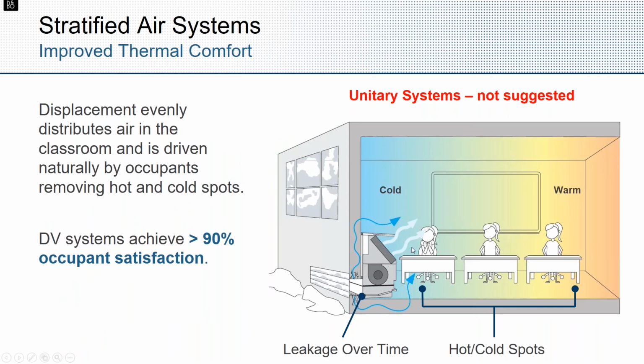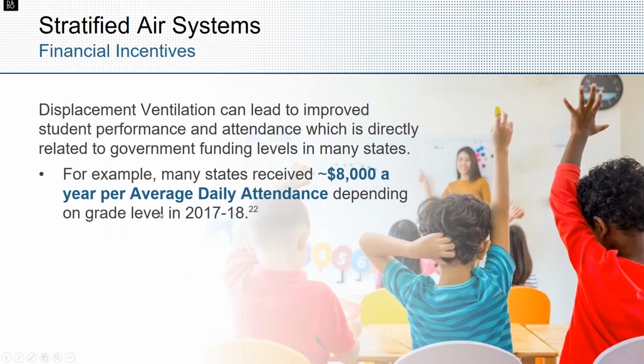Again, going back to that smoke video, displacement fills the space evenly—it's not supplying from one side of the room and trying to uniformly mix and churn the space. Because it operates on an individual thermal plume level, you really get 90%-plus occupant satisfaction, since it inherently seeks out and balances based on how much heat each occupant gives off.